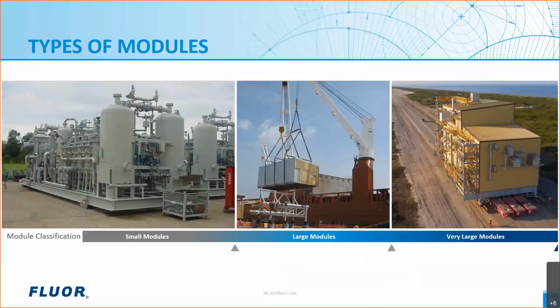Let us now discuss the types of modules based on their relative sizes, but primarily the weight. The size of a module determines how much can be installed and how the module will be transported. Modules can be designed as small or large or very large modules. Small modules are complete components of plants and can be transported by road or rail. Typically, small modules are complete packaged units that can be placed on prepared foundations and then connected to the adjoining modules. In most cases, they require minimum pre-commissioning activities. Small modules weigh less than 100 tons and are truckable and easily liftable.